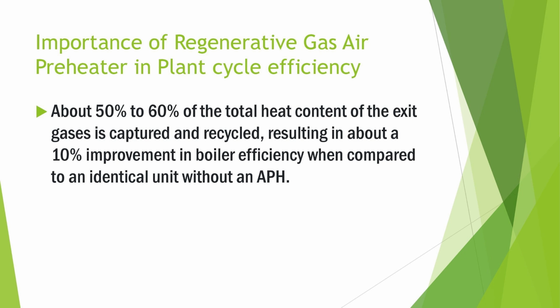Importance of regenerative gas air preheater in plant cycle efficiency. About 50% to 60% of the total heat content of the exit gases is captured and recycled, resulting in about a 10% improvement in boiler efficiency when compared to an identical unit without an APH.